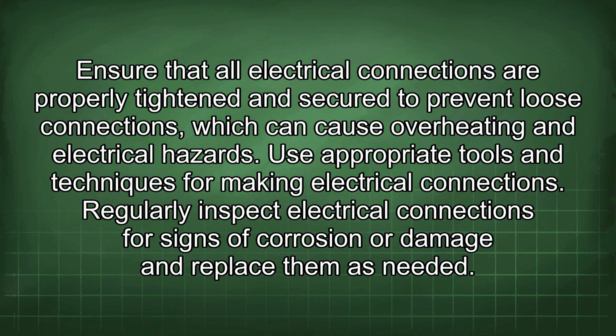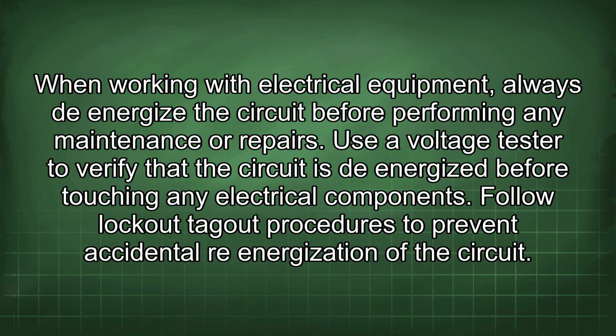Ensure that all electrical connections are properly tightened and secured to prevent loose connections, which can cause overheating and electrical hazards. Use appropriate tools and techniques for making electrical connections. Regularly inspect electrical connections for signs of corrosion or damage and replace them as needed. When working with electrical equipment, always de-energize the circuit before performing any maintenance or repairs. Use a voltage tester to verify that the circuit is de-energized before touching any electrical component. Follow lockout-tagout procedures to prevent accidental re-energization of the circuit.